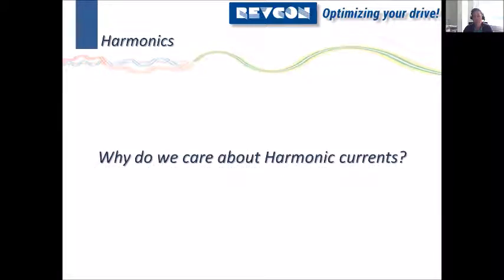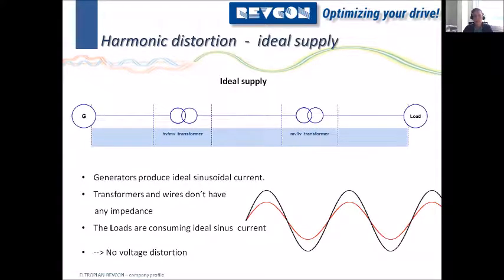So why do we care about harmonic currents in the first place? You could assume that if you have a drive that will create harmonic currents, this drive should be able to handle these currents. And as a matter of fact, they are. They don't suffer from the current. They can easily handle this higher input current. The diodes are perfectly sized to cover this.